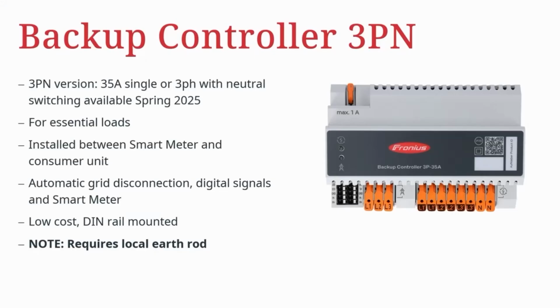We then move on to our backup controller 3PN. This is an automatic version which enables you to back up to 35 amps of devices, single or three-phase, and we're able to automatically switch between the grid tied and backup mode, and also provide that neutral switching which is required. Please make sure that the Fronius smart meter is on the grid side of the device, as this provides one of the backup fail-safe connections to ensure that the device is operating in the correct mode.